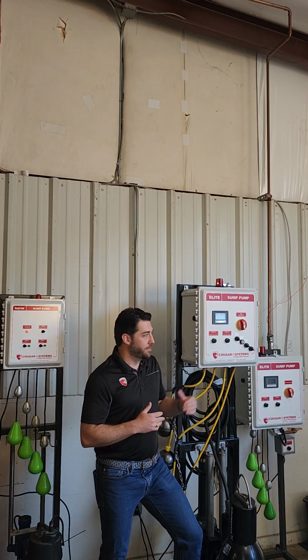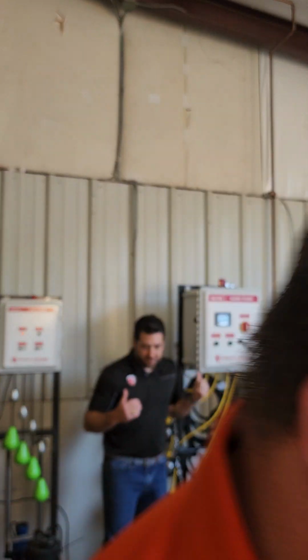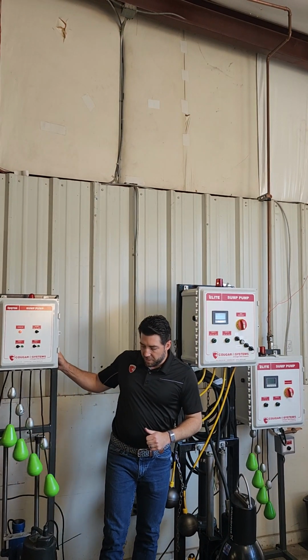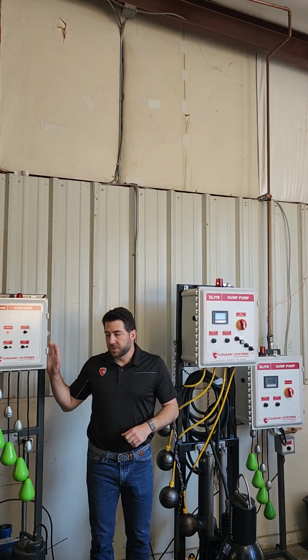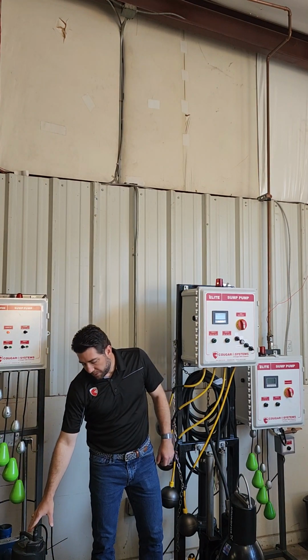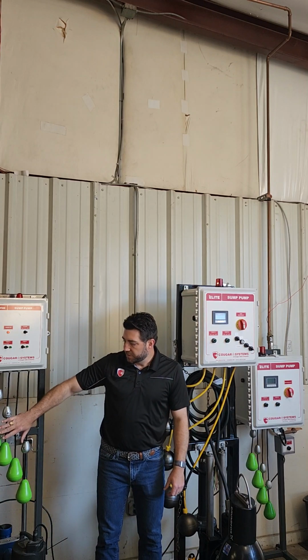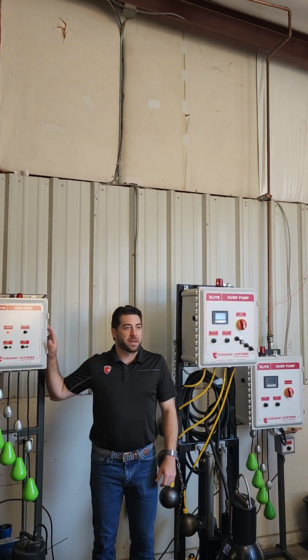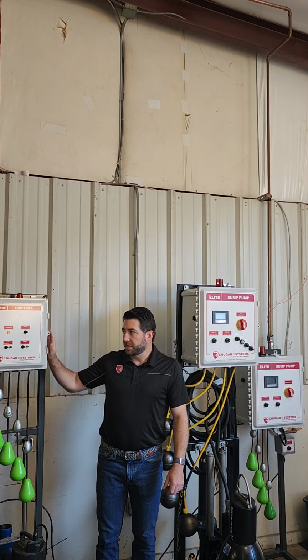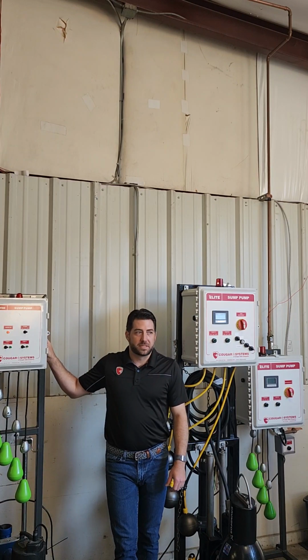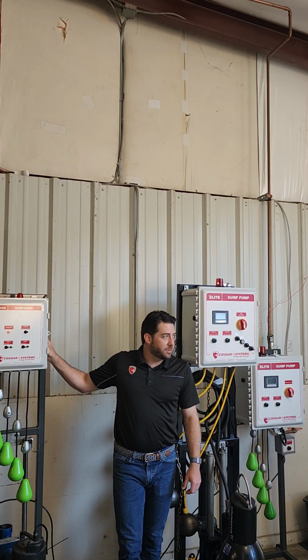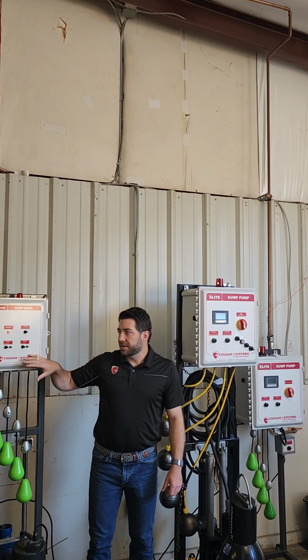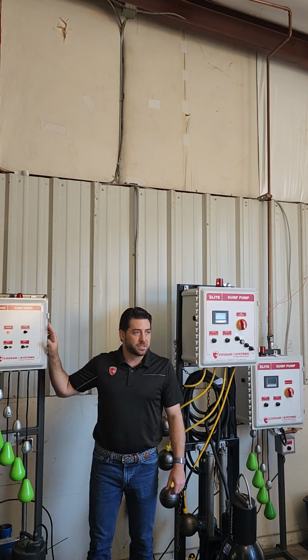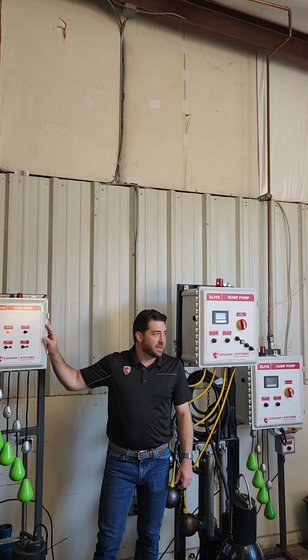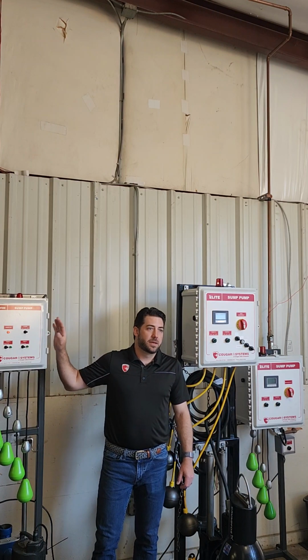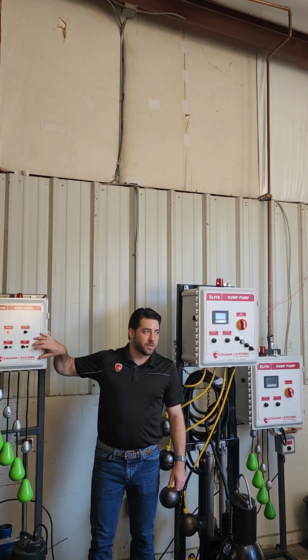So the 2 different setups that we have here, this would be our quote unquote Spartan system. So this would be a little bit smaller pumps, the entry level float switches, and our entry level panel. And this panel is really, I would say, what's typical out there for a sump pump panel, meaning it's got relay logic and it's a pretty simple system. So if the panel is out there and it was not provided by Cougar, it's likely that it's going to be these types of components.